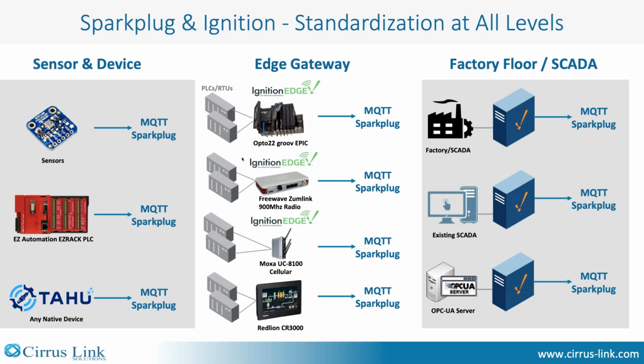Ignition Edge software can run on many different platforms and provides a tool that configures connectivity requiring no custom code. It has a set of protocols to connect to assets, create tag naming and metadata, and provide the context to make it IT consumable. The transmission module on Ignition Edge converts the OT tags into MQTT Sparkplug data using report by exception for efficient bandwidth, and utilizes store and forward capabilities in case of network failures.